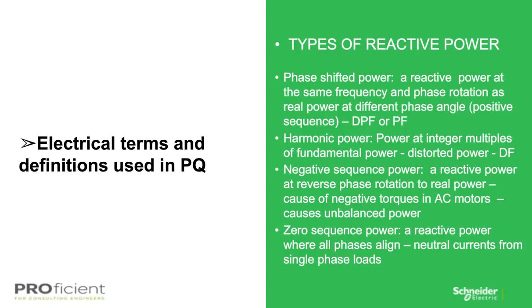The next two, I don't want to spend too much time on, as I really want to focus on both phase shifted power as well as harmonic power, but for all intents and purposes, I'd like to quickly review the definitions. Negative sequence power is caused by single loads connected to neutral or phase-to-phase on a three-phase source. The result is unbalanced power flow per phase. As far as AC motors are concerned, negative sequence power causes reverse torque, and much damage could be associated with that. It also manifests itself as unbalanced current on a three-phase supply.